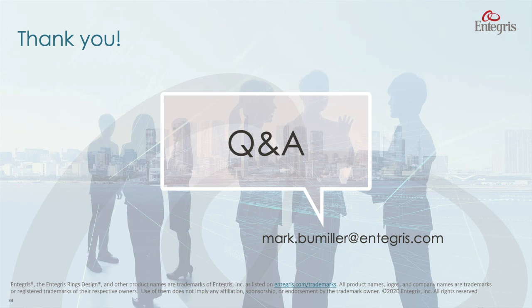Wonderful. Next question is, is there automation software available for system suitability calculations for method 1 of USP 729? Yeah, I haven't heard that question before. So if we're doing method 1 and we're using dynamic light scattering, can we automate that? And there's some things we can do other people can't do. And that includes, for instance, those, remember, are high concentration samples, and we can have an auto diluter built into the NICOMP.